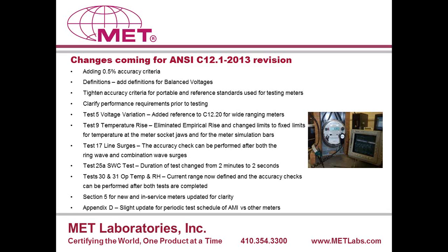The standard is going to have 0.5 accuracy criteria added to it, and it really has to do more with the C12.20 standard, which already has 0.5% accuracy criteria in it, but there are certain meters, depending on the configuration in the field, that are not considered a Blondel meter. So you may be able to test those.